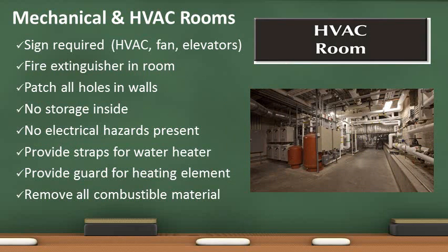Inspect mechanical and HVAC rooms for electrical hazards, such as missing cover plates, broken conduit, and electrical panel issues. Combustible storage is not permitted in these rooms.